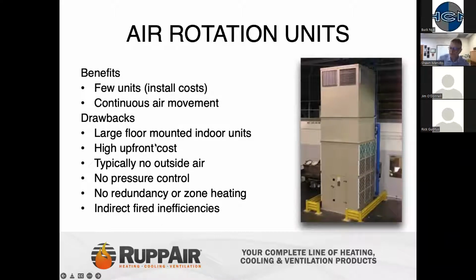The biggest drawback is the floor space that these occupy. They take up a lot of floor space, which now in these warehouses, the floor is basically the value. High upfront costs, very high upfront costs. Typically no outside air, no pressure control, no redundancy. That's the biggest thing, because you can get by with maybe one unit to cover a big area. There's no redundancy. If this unit goes down, it goes down. And obviously the indirect fired inefficiencies.